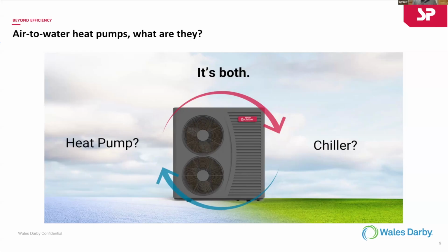The other thing about this that we'll talk about is that it's an all-in-one appliance. So it's like a refrigerator. You basically take it out of the box, drop it next to the house, plug it in, and you're kind of good to go. There's no requirement for the AC guy to run refrigerant lines and deal with all the complications of refrigerants. Did I size the piping right? How long did I run the piping? How much refrigerant did I put in? Setting the pressures and getting all the air out, and all those issues that come up with running refrigerant. This is not the case, because this is a whole enclosed system where you don't touch the refrigerant side of things. You're just touching the water.